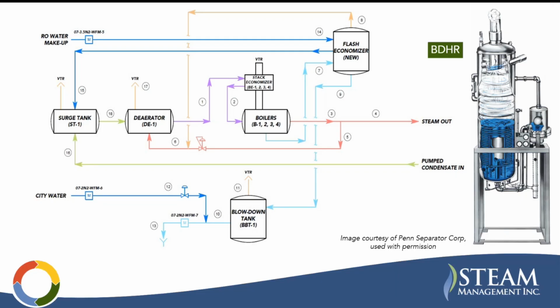The drain is going to settle down here, or the liquid is going to settle down here. That's going to be a heat sink for this makeup water coil that you can see. The makeup water is going to come in, be preheated, and leave. That's shown here. And then the drain is going to continue on to your bottom blowdown tank, but it is going to be significantly cooler than it would have been otherwise.